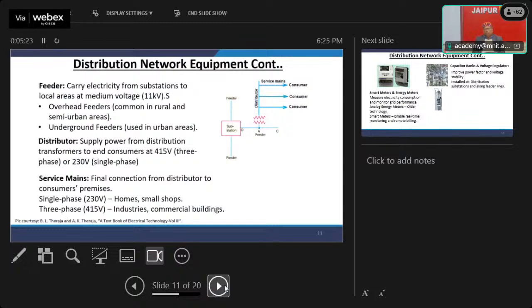And then we talk about feeder, a very commonly used term. Feeders carry electricity from substation to local area at medium voltage. Overhead feeders are common in rural and semi-urban India. Underground feeders are common in urban areas. Distributors supply power from distribution transformer to end consumers, that is 415 volt, three phase to 230 volt, single phase supply. Then you have service mains, 230 volt for homes and small shops. Industries and commercial buildings will have 415 volt.